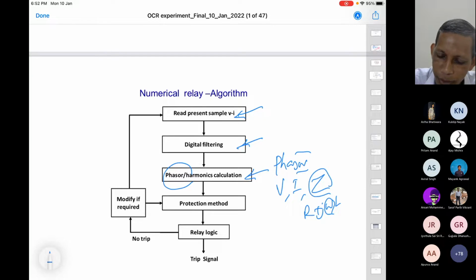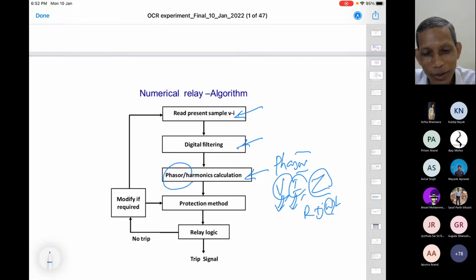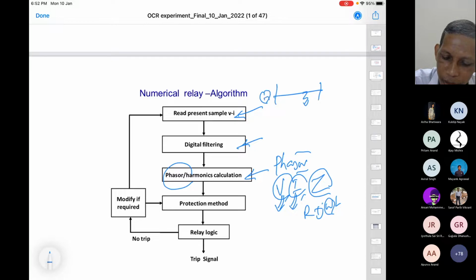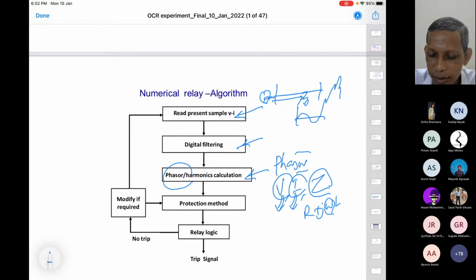So when you talk about impedance and you relate to the voltage and I, these voltage and currents are not the RMS voltage and currents, rather they are the fundamental component of voltage and current. Why are we talking about fundamental here? Whenever a fault happens in the system, let us say this is the source, the corresponding current and the voltage go into a transient process. Agree? It goes from the normal situation of R and L to another R and L. So let us say the normal current flowing is like this, and then suddenly the current becomes like this. At that time, the voltage will be low, and that will also be distorted.